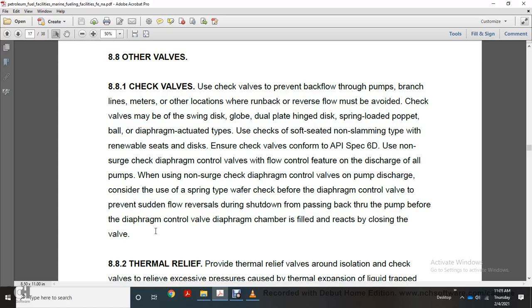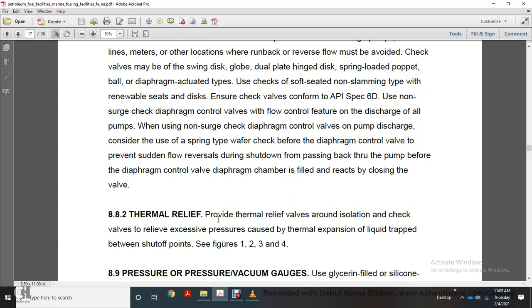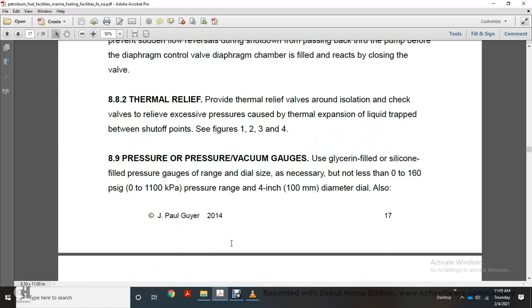Use a non-surge check valve with the diaphragm control valve with the flow feature at the pump discharge valve. When using a non-surge check valve with the control valve at the pump discharge, use a spring type with a wafer check before the diaphragm control valve, to prevent reversal of flow during shutdown from passing back through the pump, before the diaphragm control valve diaphragm chamber is filled and the valve closes. Thermal relief valve: provide thermal relief valves around isolation check valves that relieve the excessive pressure caused by thermal expansion of liquid trapped between shutoff points, see figures 1, 2, 3, and 4.